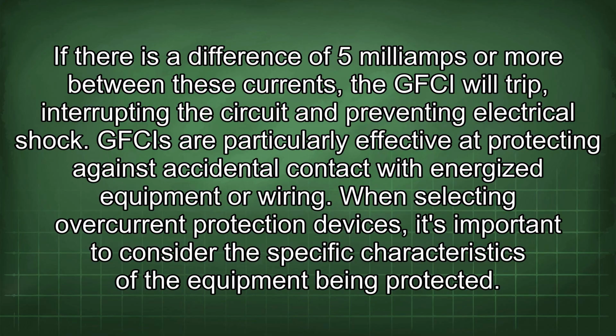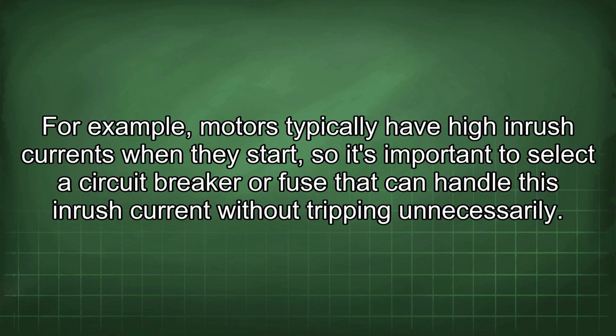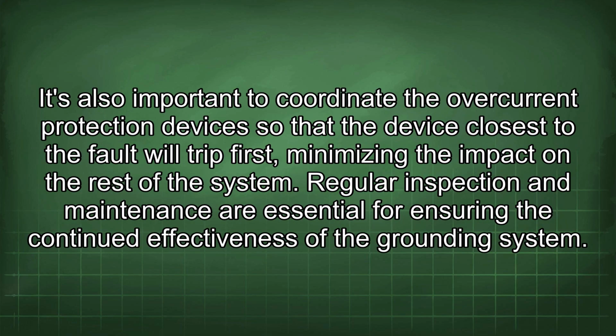When selecting overcurrent protection devices, it's important to consider the specific characteristics of the equipment being protected. For example, motors typically have high inrush currents when they start, so it's important to select a circuit breaker or fuse that can handle this inrush current without tripping unnecessarily. It's also important to coordinate the overcurrent protection devices so that the device closest to the fault will trip first, minimizing the impact on the rest of the system.